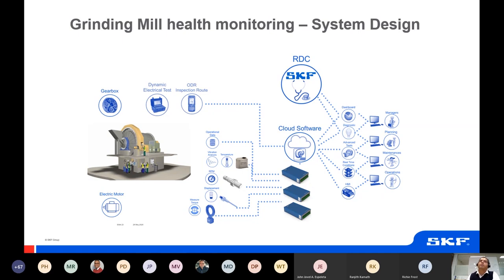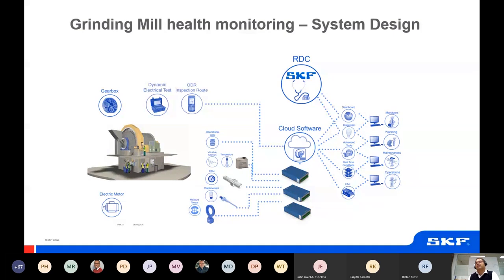For the trunnion bearing — a very slow speed application — we can still pick up bearing failure using vibration sensors. Even though the low-frequency cutoff of the vibration sensor may be higher than the running speed, running speed has nothing to do with the modulated energy from the bearing, and that's what we're interested in to detect bearing failure. Let's look at some spectra and time waveforms.